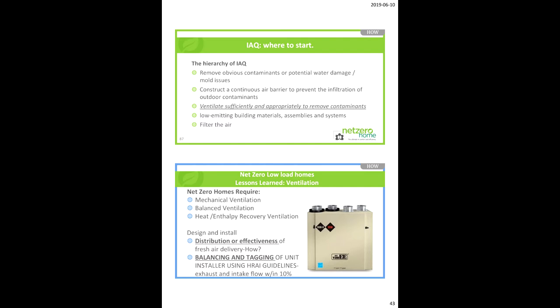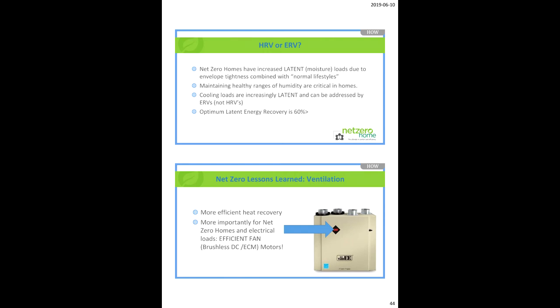HRV or ERV? How many of you are using ERVs? Sort of cool, isn't it? 8 years ago, I Googled ERVs and it told me I couldn't install them north of the Mason-Dixon line. ERVs typically only used in warm climates. Some manufacturers say you can't do that, the core's going to freeze up and the door's going to shut on you all winter, you're not going to get fresh air. Well, just wait a minute.